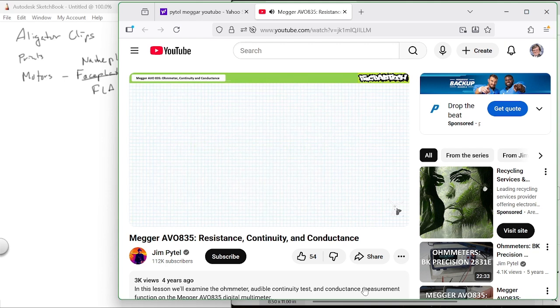On a very basic level, ohm meters are commonly employed to check the continuity of a circuit. Forget measuring resistance in units of ohms. Is something connected or is it not connected? Opens, i.e. items with no conductive path, would be identified with an OL on display. In contrast, items with a conductive path would be identified with a small resistance value on the display.